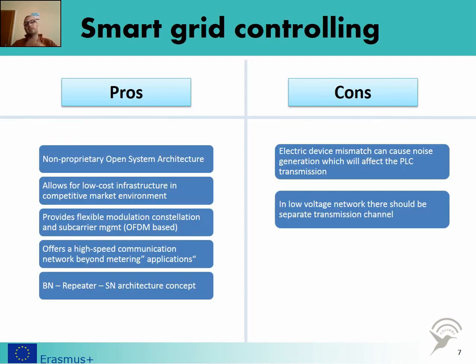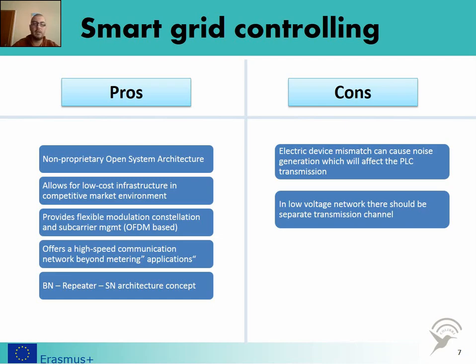There are some pros and cons of using wired communications. The pros are as follows: it is a non-proprietary, open system architecture. All we need is the existing electricity wire, which allows for low-cost infrastructure in a competitive market environment — no additional infrastructure is needed. It provides flexible modulation, constellation, and sub-carrier management, which is implemented by OFDM modulation, creating sub-carriers. This offers a high-speed communication network beyond metering applications, which means it can also be a carrier for internet access at your home.